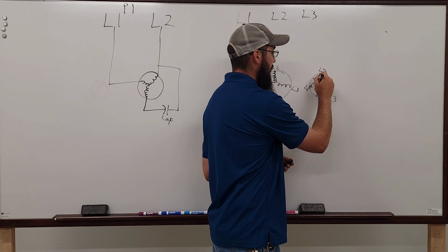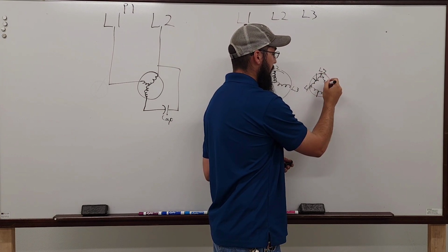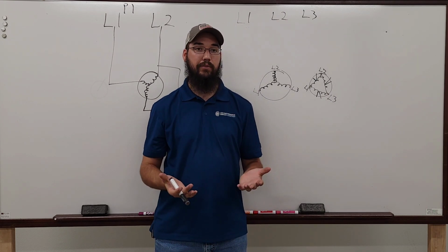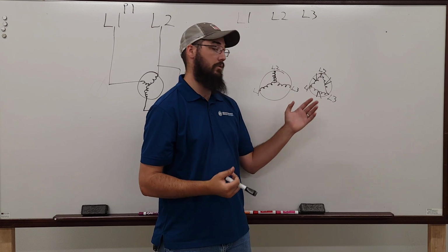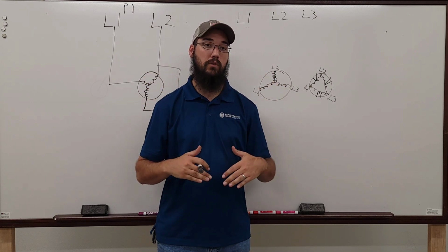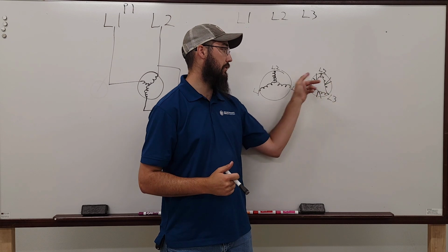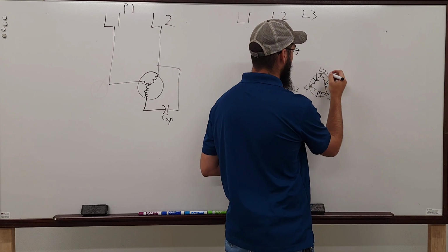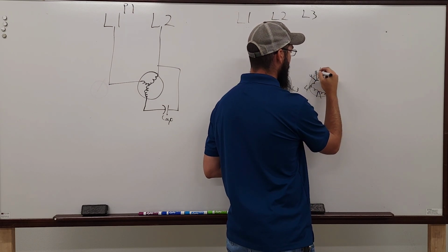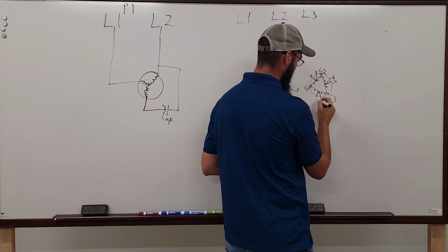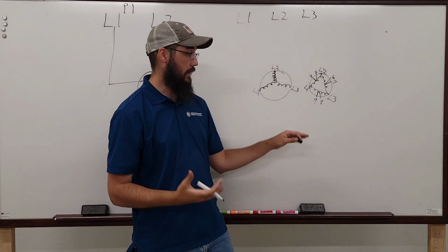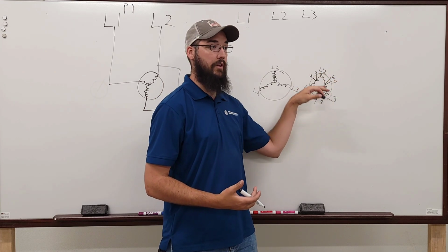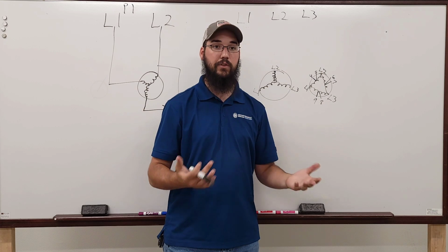And that's literally right here in the middle of the winding where it splits off. And depending on the voltage you have, that's where you get to high voltage or low voltage, will depend on how you configure these wires. So let's say this will be 1, 2, 3, and this may be 4, 5, 6, 7, 8, 9. And then on the pecker head, it'll tell you which configuration to use depending on the voltage you have, right?